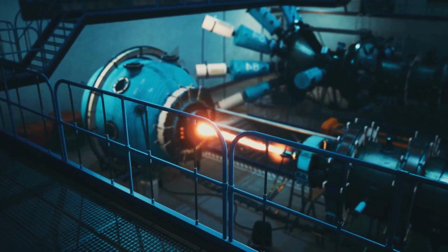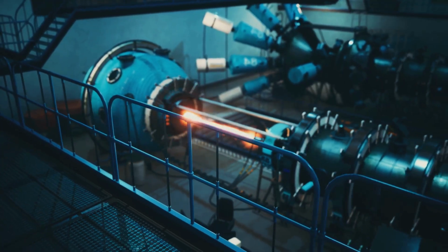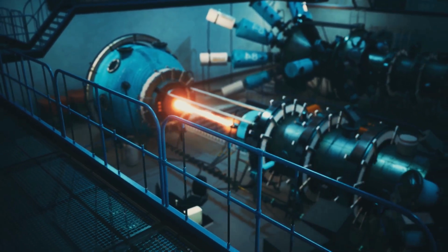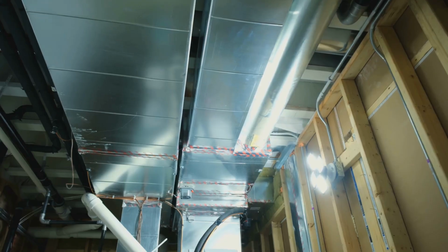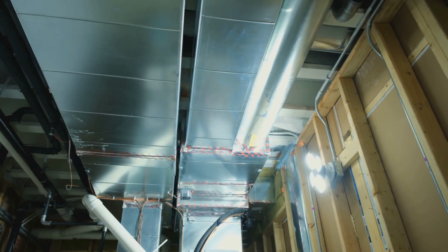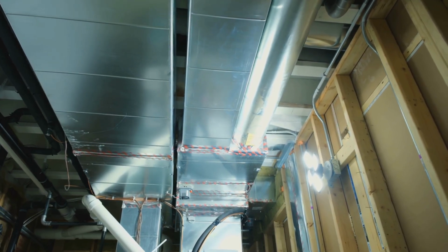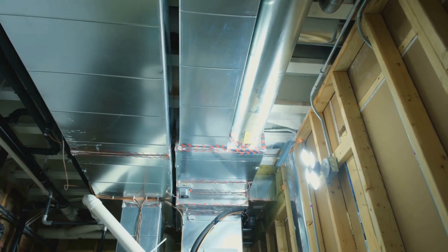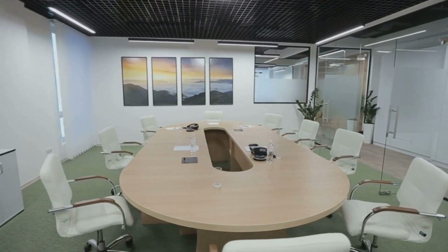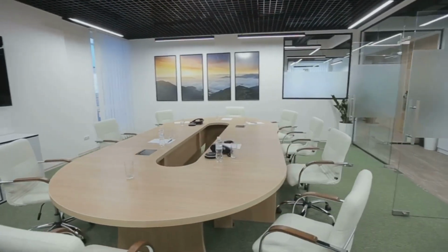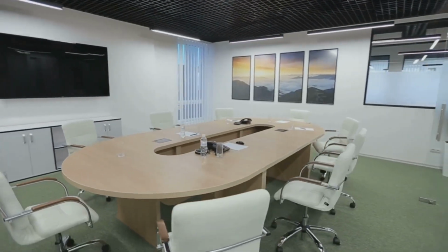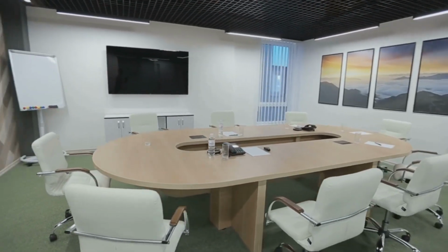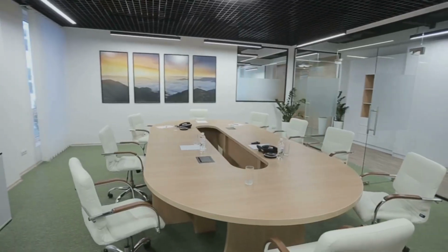High-efficiency chillers and boilers. For larger hotels, select high-efficiency water-cooled chillers and condensing boilers. Energy recovery ventilation, ERV. ERVs are essential for maintaining fresh air while saving energy. They transfer heat and humidity from the stale exhaust air to the incoming fresh air, preconditioning it and reducing the load on the HVAC system. Demand-controlled ventilation. Use CO2 sensors in high-occupancy areas like conference rooms and ballrooms to adjust ventilation based on the actual number of people present, saving energy when the spaces are empty.